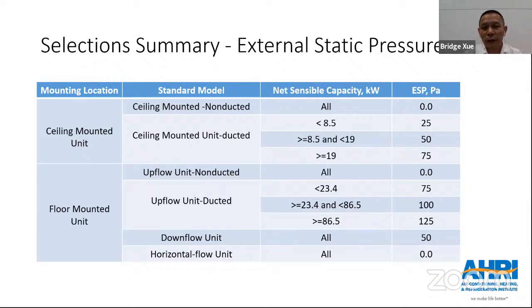So I'm going to deliver different external static pressure because it's going to impact the design. So you can see here the floor mounted units, right? Including ducted and without ducted for sure. For the non-ducted unit, the external static pressure will be 0 Pascal. But for ceiling mounted ducted unit, they have three different ranges. The first one is if the unit capacity is less than 8.5 kilowatts, 25 Pascal will be applied. For the medium size from 8.5 to 19 kilowatts, 50 Pascal will be applied. For the largest unit, which is greater than 19 kilowatts, 75 Pascal will apply.